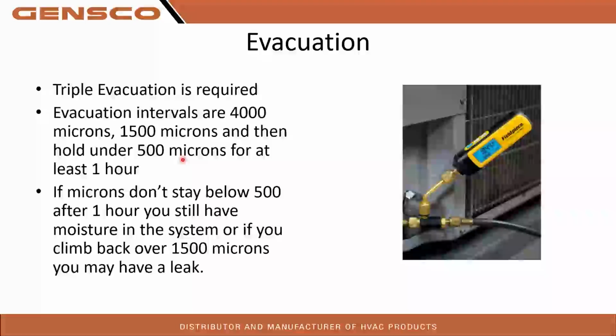If you're struggling to get your microns down past that 500, ask yourself, when was the last time you changed your vacuum pump oil? Once vacuum pump oil starts getting dirty, guess what? That's considered part of your system while you're on vacuum. Your vacuum pump is trying to pull contaminants out of that oil as well. So make sure to do regular oil changes on your vacuum pump. That black gold isn't too terribly expensive, it's cheaper than replacing a vacuum pump, and it's going to save you time and give you a better vacuum.